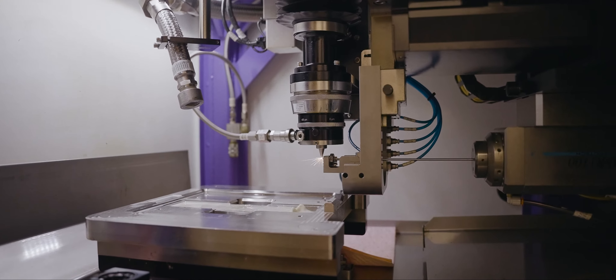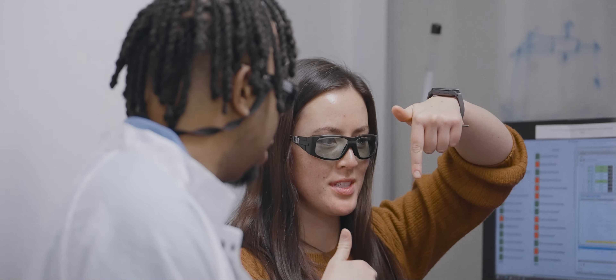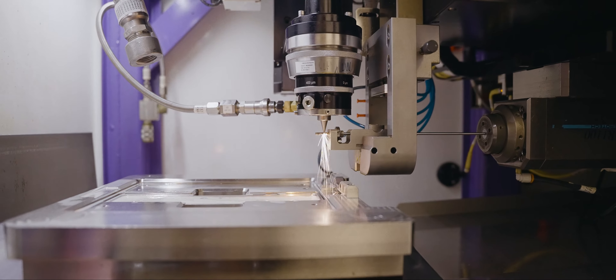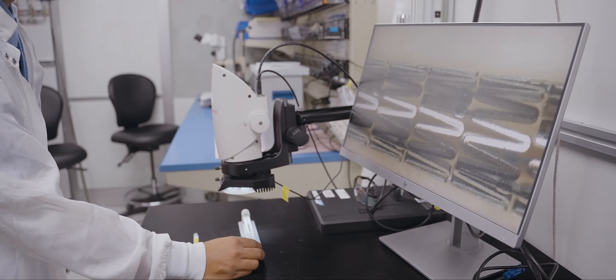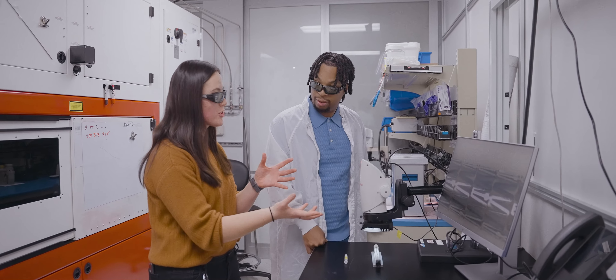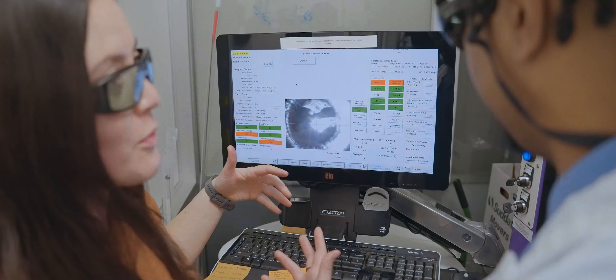The tube is rotating underneath and the laser is on top, so as it's rotating and translating it's cutting a pattern — imagine like puzzle pieces. This is what we actually cut — all the way down here — this is our stent. Up on the screen under the scope there's a lot of detail. Imagine this like a Chinese finger trap; this is what opens up your vessels so you can have blood flow.